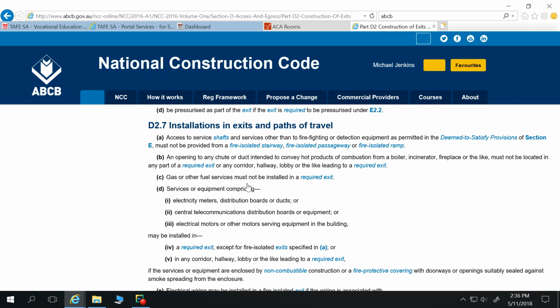Services or equipment comprising electricity meters, distribution boards or ducts, or central telecommunications distribution boards should not be located in a fire isolated stairway. Can you think of why that would be the case? I think, for starters, one of those things might actually be the source of a fire. And if we've got a distribution board in a fire isolated stairway and things are shorting out and starting to melt, then what do the people do? If there are two exits, they can use the other exit, but in a building this has to cater for all.